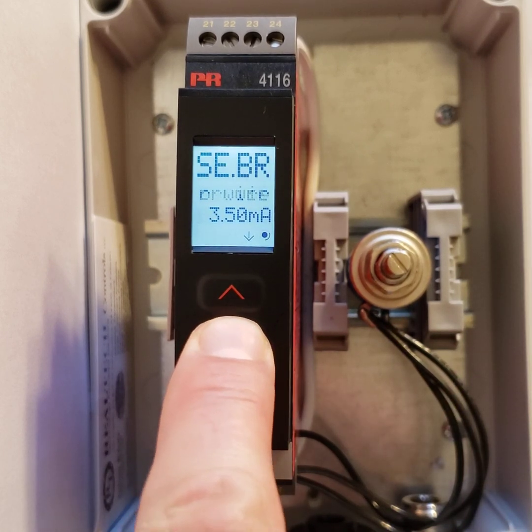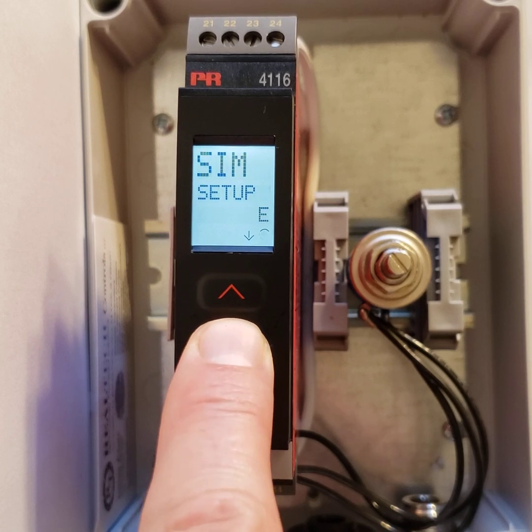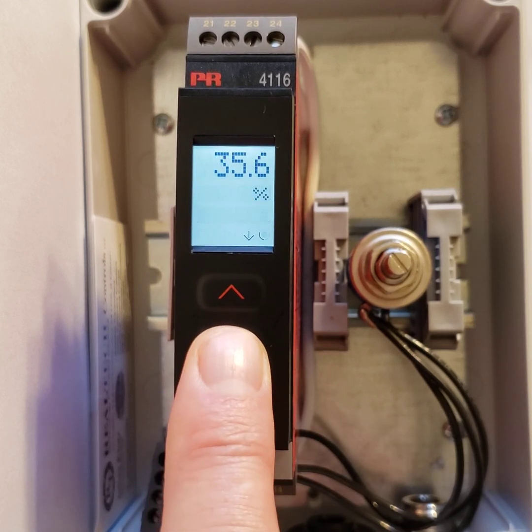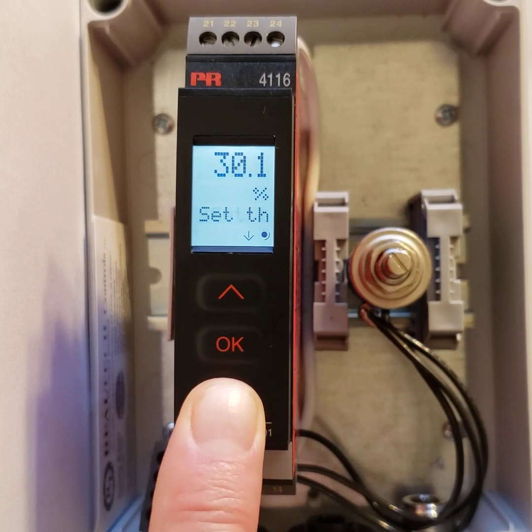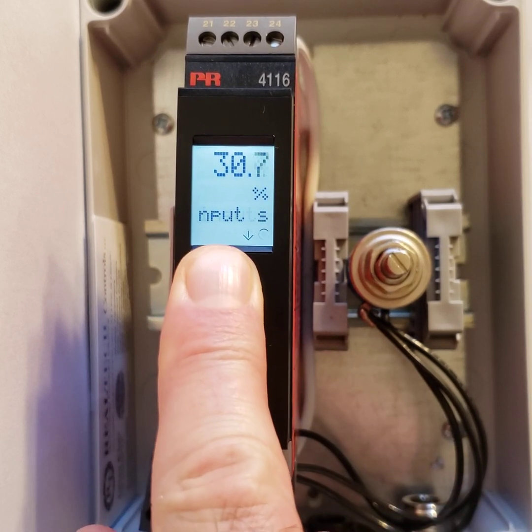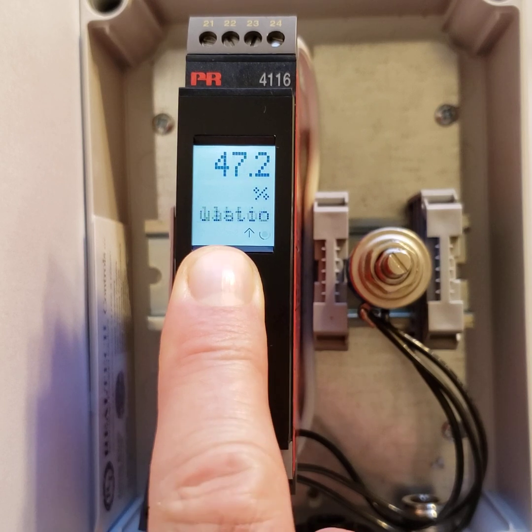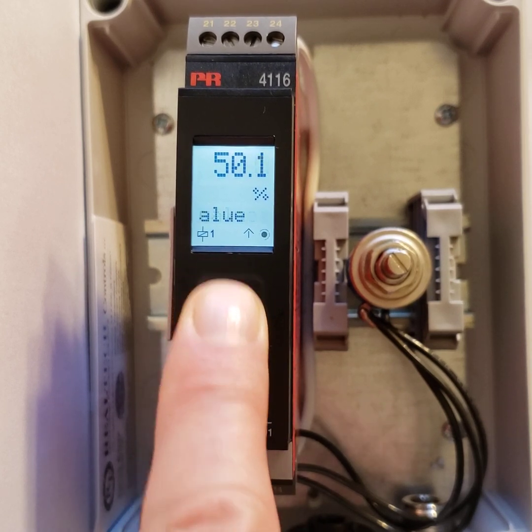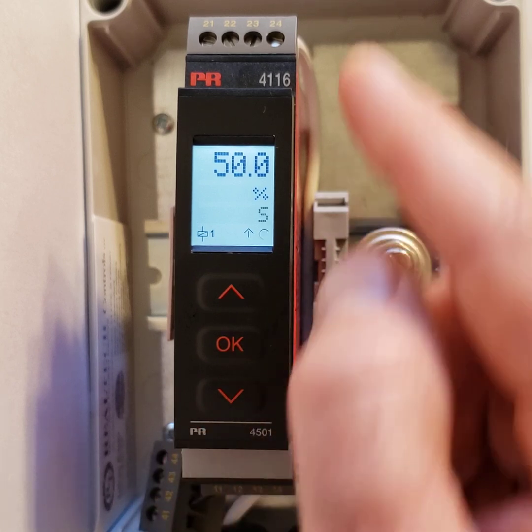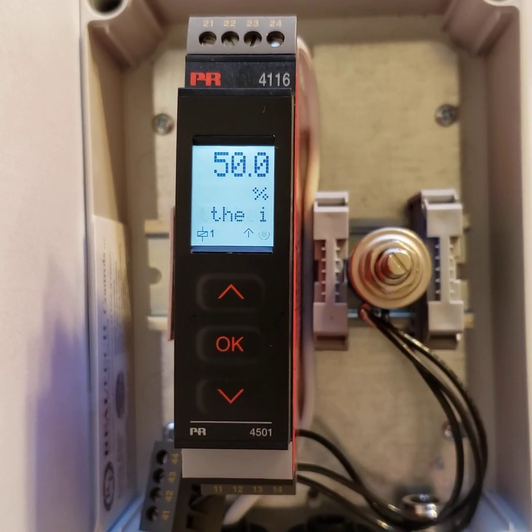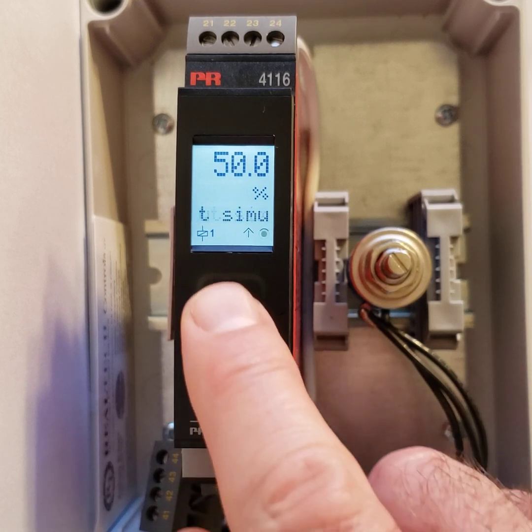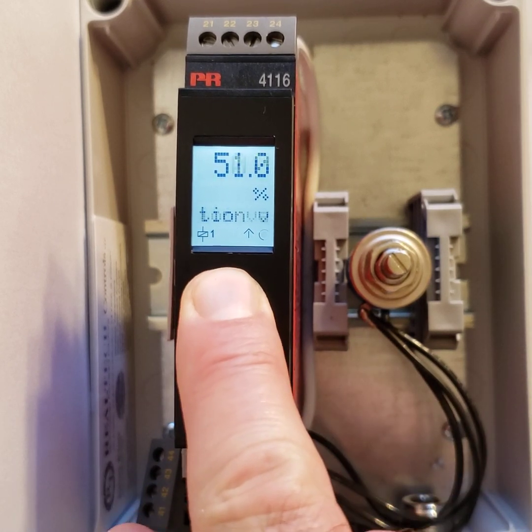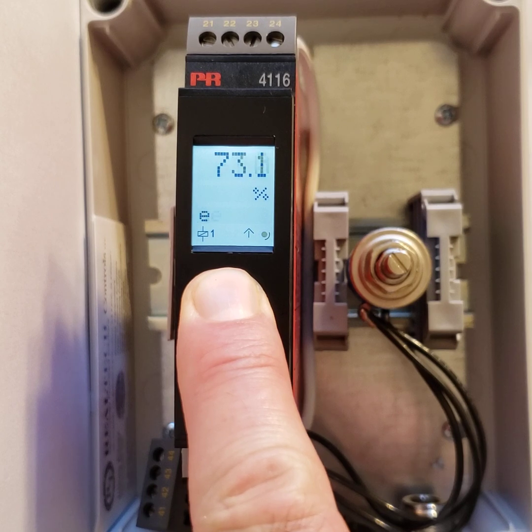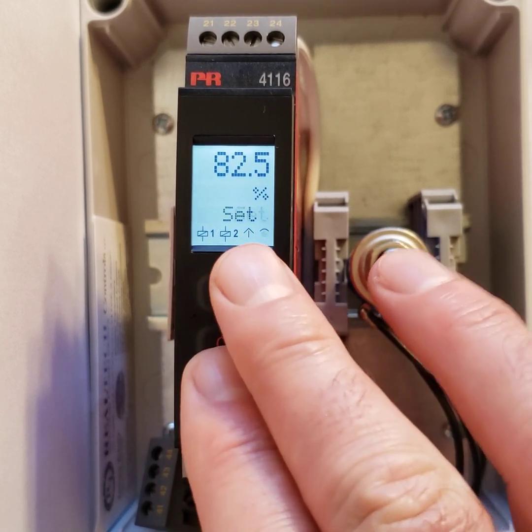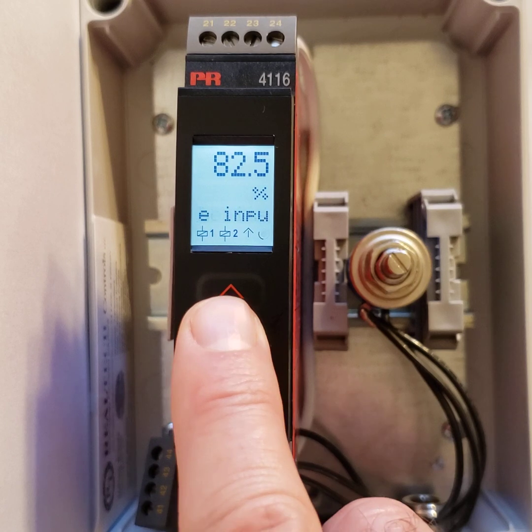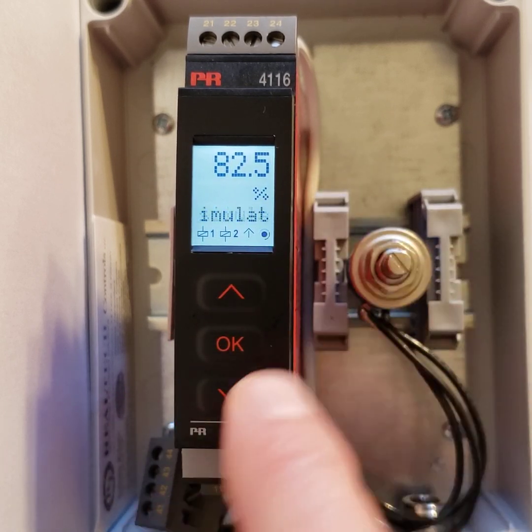I can go into the advanced menu. I can go simulate, enable simulation, yes. Now I'm actually simulating what the pot should be. So if I move this up and down, that's actually simulating a physical input. And you'll see that if I have 50%, you'll actually be getting your milliamps out of there at 12 milliamps. And also it still works the relays, as you can see at the bottom, your relays still function as if the potentiometer was connected. But I'm just using the top display for simulation. So that is the output simulated from the input.